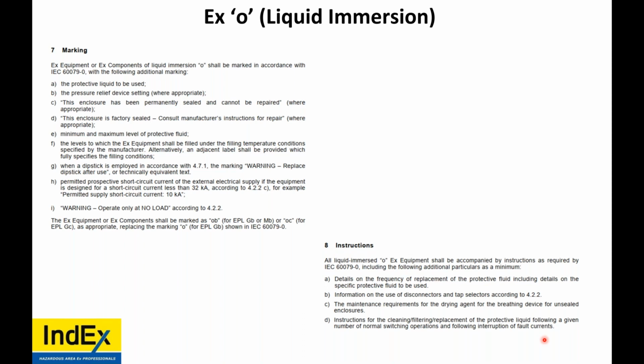So interruption, meaning how many times has the transformer been turned on and off? The more you turn it on and off, the more wear and tear you put on it. Also during fault currents, so short circuits, overloads, too many lightning strikes, anything causing a fault current, an inspection obviously needs to happen. Make sure that nothing has broken down, no insulation.